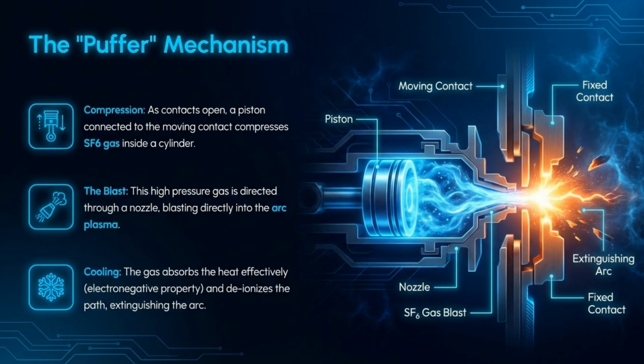Here is a visualization of the puffer mechanism. Compression moves the piston, compressing SF6. The blast directs the gas into the arc. Cooling is achieved as the gas deionizes the path and extinguishes the arc.